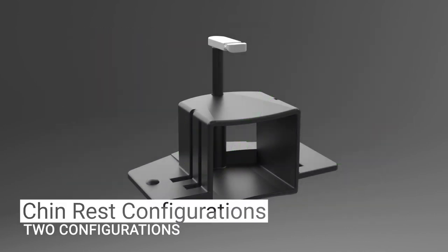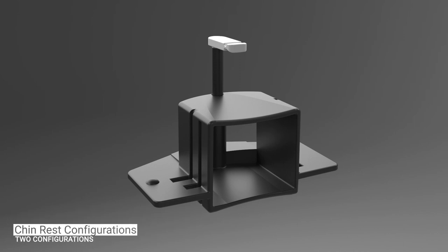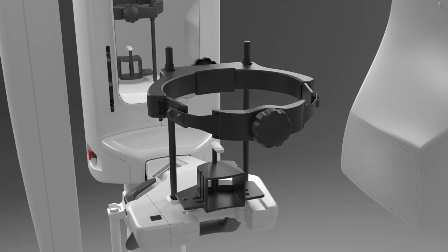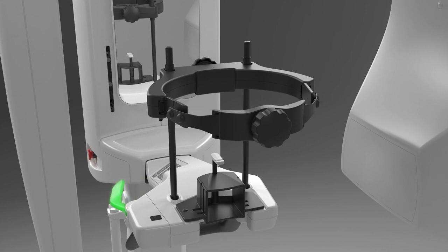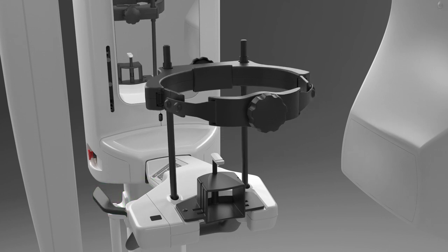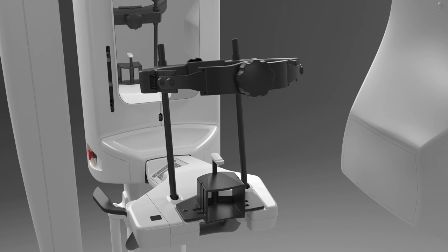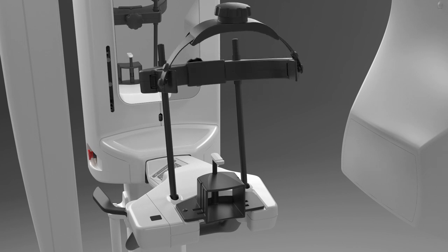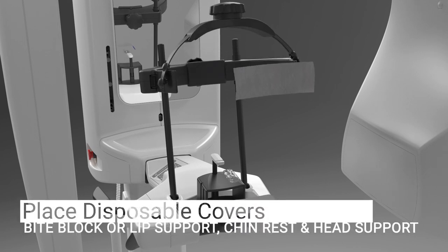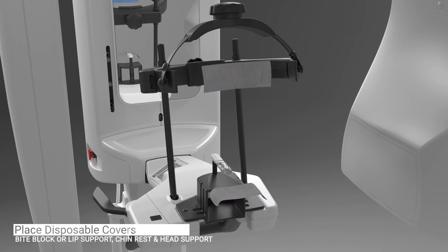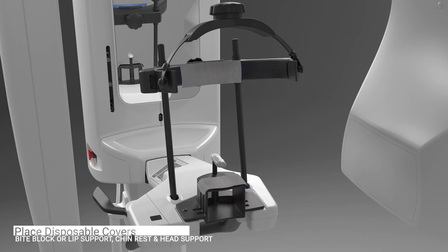There are two chin rest configurations that can be used when acquiring a 2D panoramic image: Standard Panoramic and Pediatric Panoramic. Both require the bite block and chin rest, except for edentulous patients that require the use of the lip support and chin rest. Pre-configure the chin rest and place it into the system. Release the head support locking lever and move it towards the patient mirror. Pivot the back portion of the head support into its upright position. Place disposable covers on the bite support or lip support, patient chin rest, and head support.